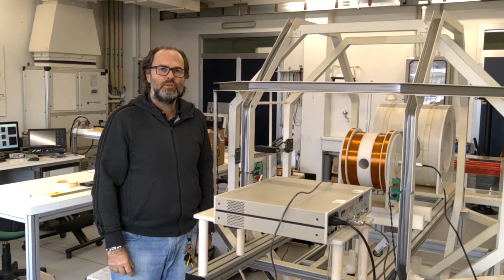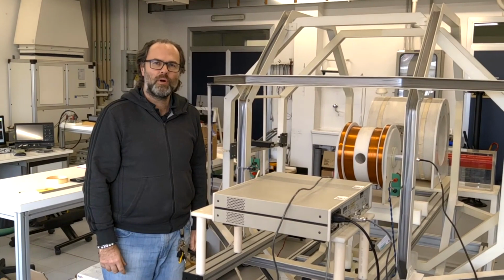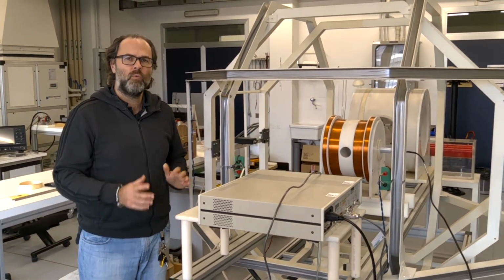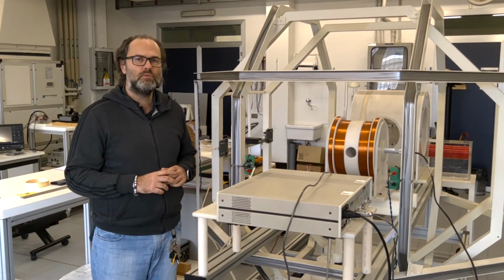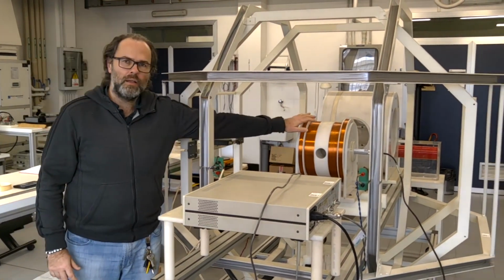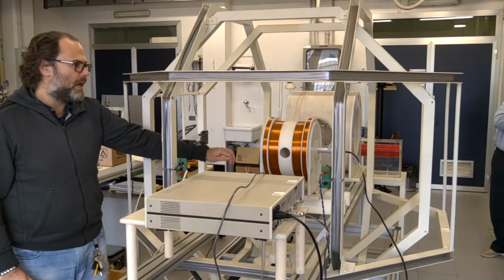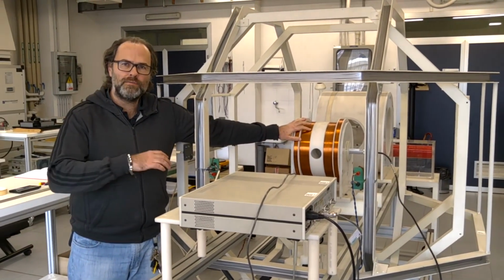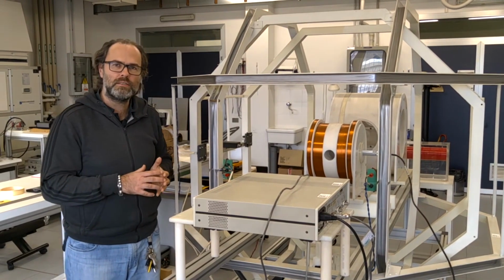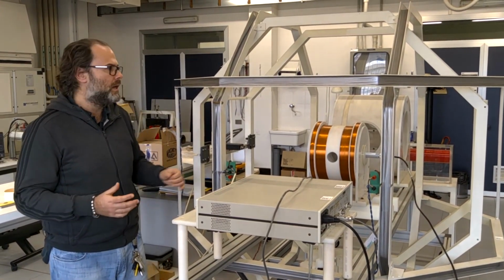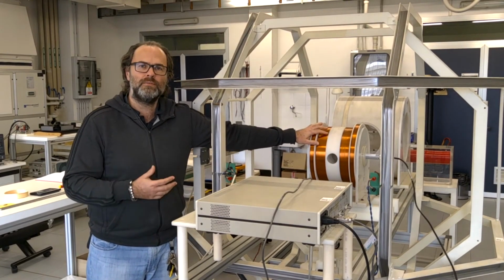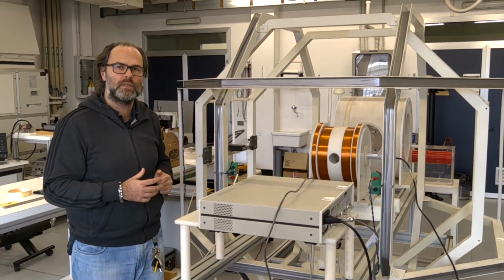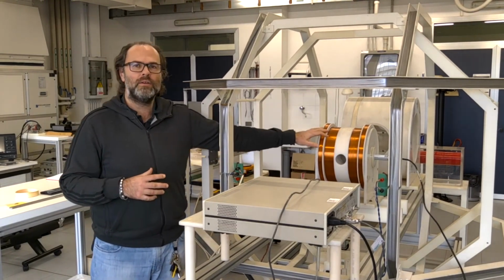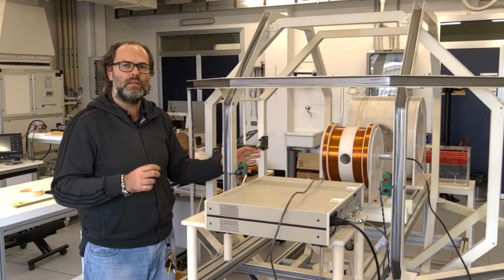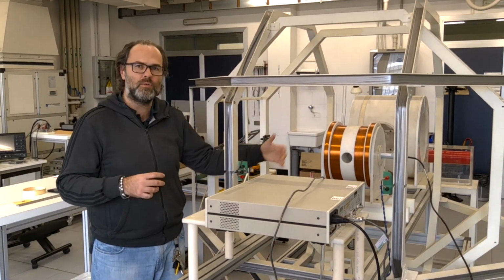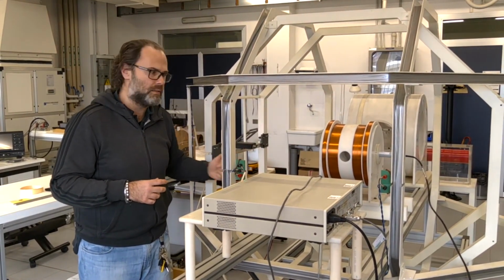In this video, I will show you how we calibrate a magnetic field probe in the range 1 to 20 millitesla. In order to do that, we need a coil that is used to generate a magnetic field, and this coil is the transfer standard from the nuclear magnetic resonance and the probe that we want to calibrate. It is the transfer standard because the coil itself has been calibrated with the nuclear magnetic resonance experiment in order to determine the proportionality value between the electric current that flows into the windings and the applied magnetic field.